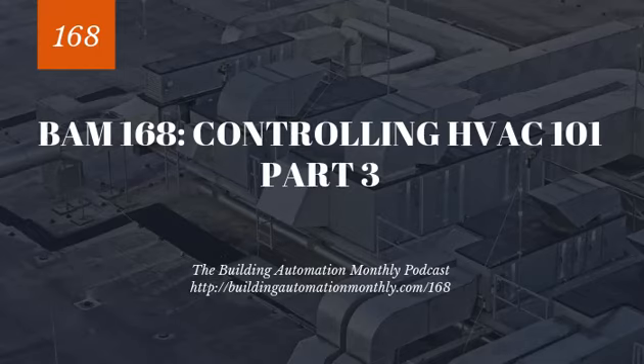The last thing I want to cover in this episode, because I realize it's getting a little long in the tooth now, is lead lag and partial load control. So lead lag is quite simply rotating pieces of equipment so that you don't run them constantly, so that they have a longer life. Pretty straightforward, right? And you can also use lead lag when something fails. You go over to the lag, and you could do this for chillers, for cooling towers, pumps. You can run lead lag across the spectrum of all these systems, right?